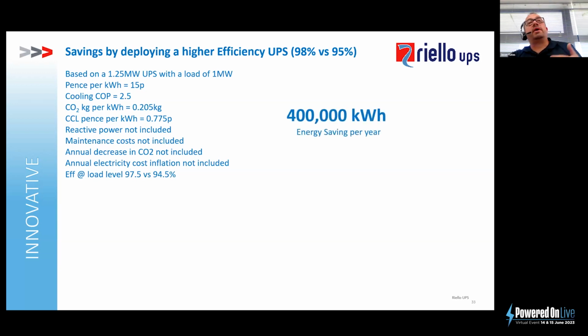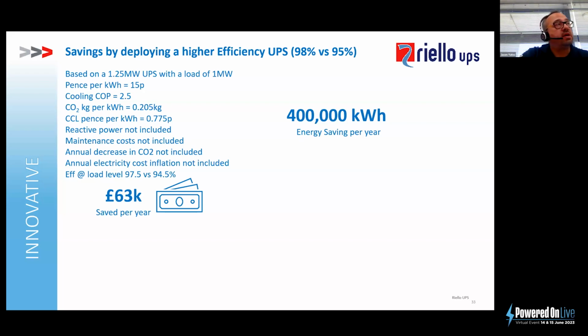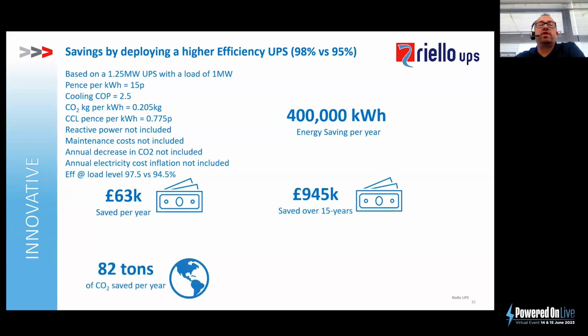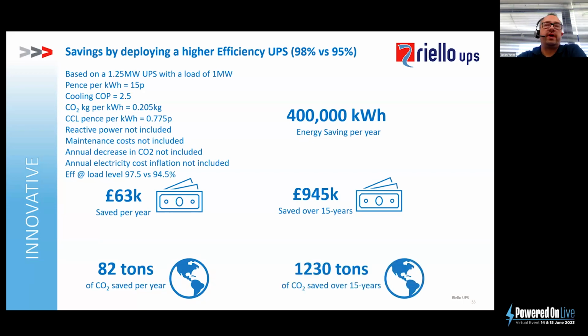So if we look at that, by deploying a 98% efficient UPS versus a 95%, we could make savings of over 400,000 kilowatt hours per year. This equates, based on 15 pence, to £63,000 per year saved. Over 15 years, that's nearly £1 million. Over a year, we would save 82 tons of CO2, and over 15 years, over 1,230 tons of CO2.